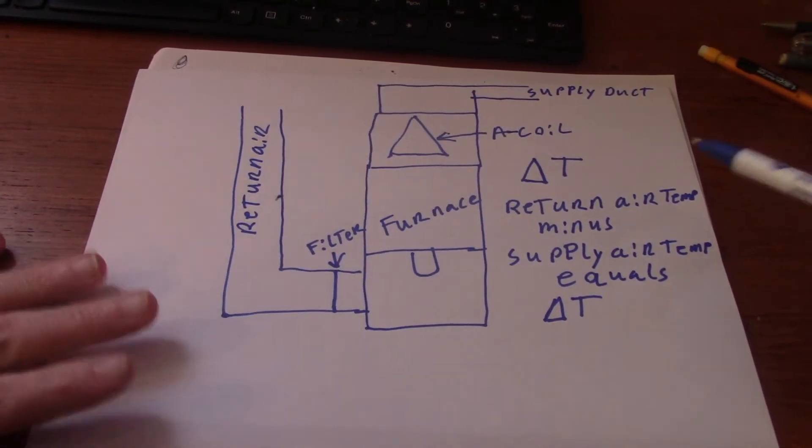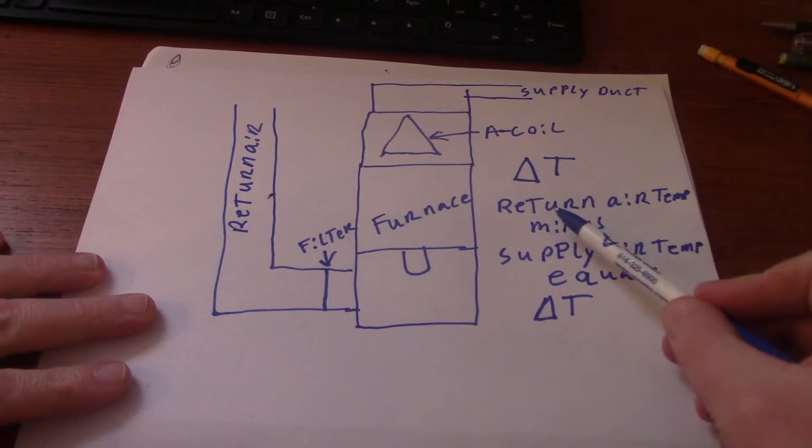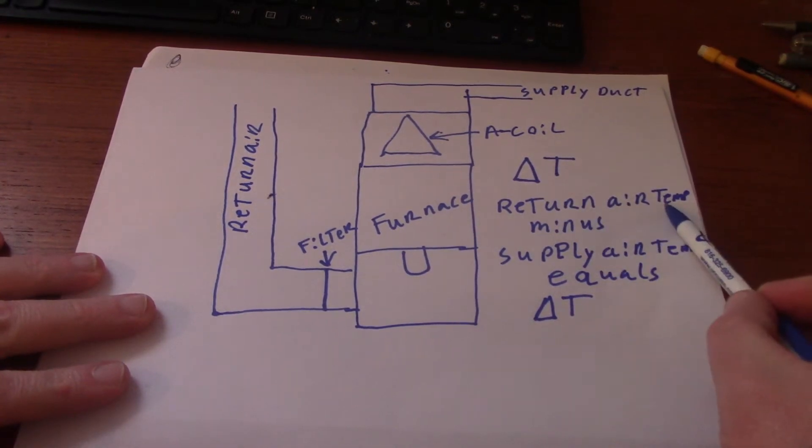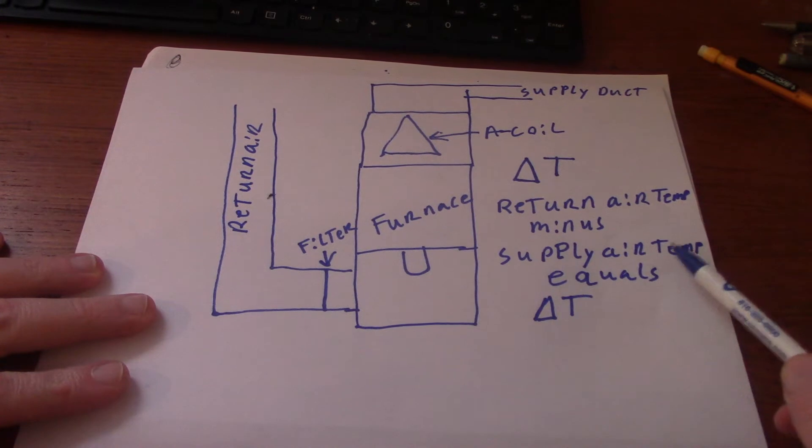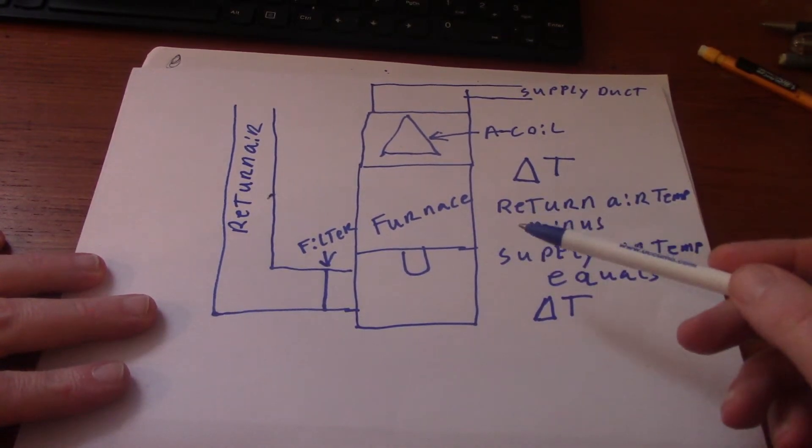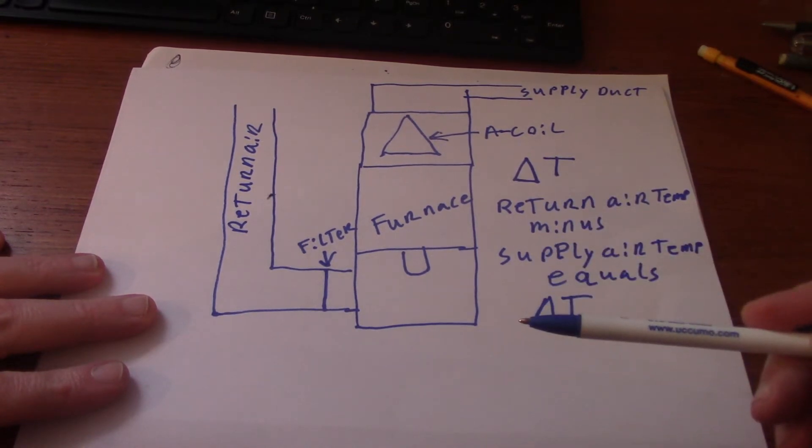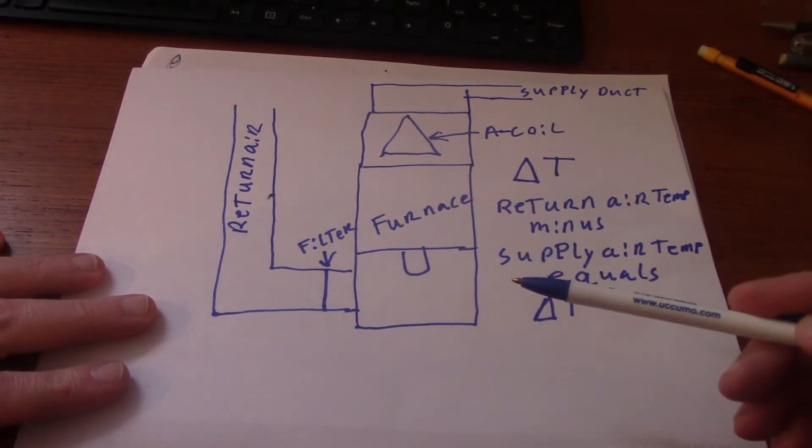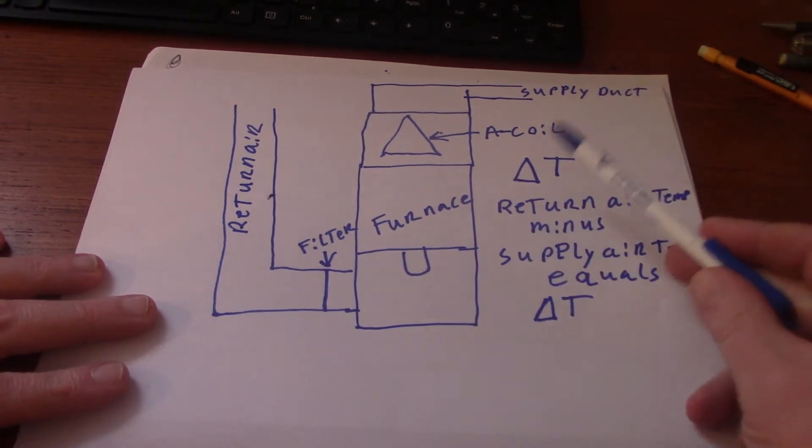To calculate it, you take your return air temperature minus supply air temperature will equal Delta T. This is different than evaporator Td. Some people may also call this temperature drop, but it's not the same as evaporator Td. It's Delta T.